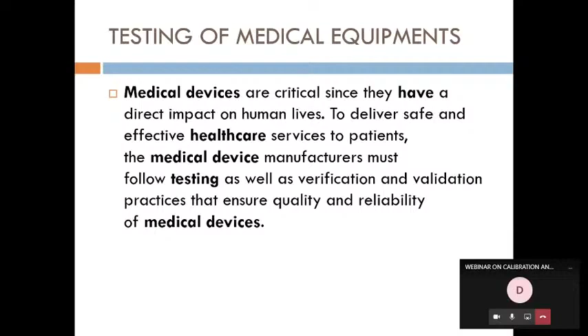First we are going for the pulse oximeter. How do you test the machine? This is a pulse oximeter, and here is a probe, and here is the extension cable. Once you connect this pulse oximeter to your finger, if there is no value, first thing you need to change is the extension cable. You change the extension cable from another machine and connect the same probe to the machine. If the value is okay, then it was an extension cable problem. And if after changing the extension cable the problem remains, then you change the probe.